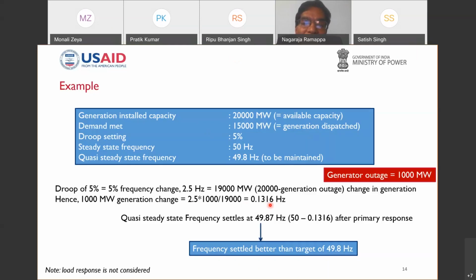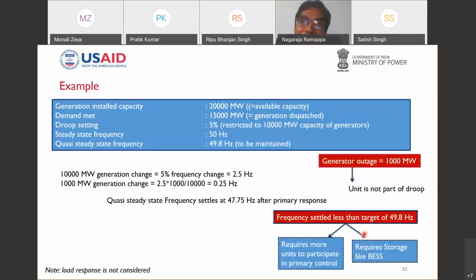Therefore, quasi-steady state frequency becomes 49.87 Hz, that is 50 minus 0.13, after the primary control. Therefore, frequency settles better than the target of 49.8 Hz at the end of the primary control. We need to understand governor role, and making the machines participate in the primary control is very, very important.